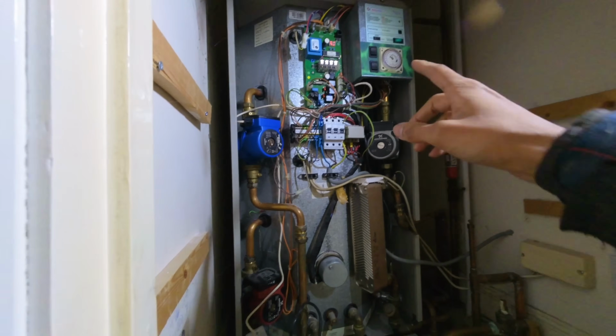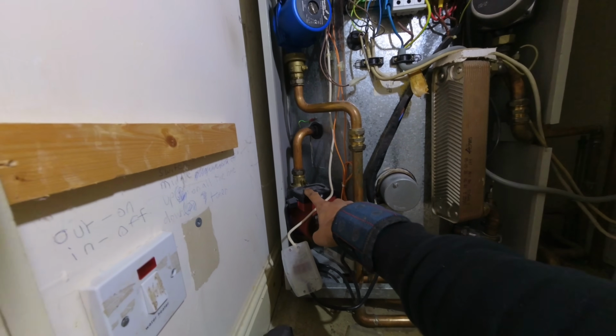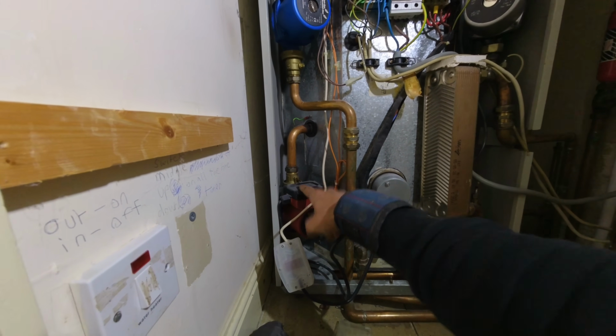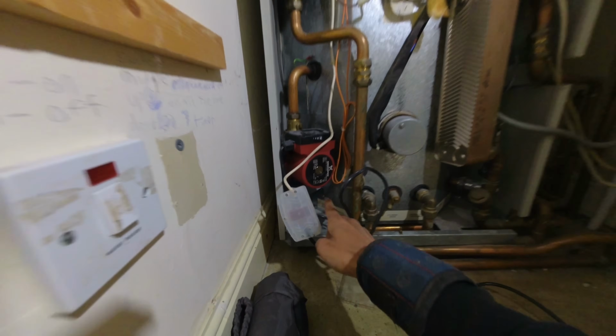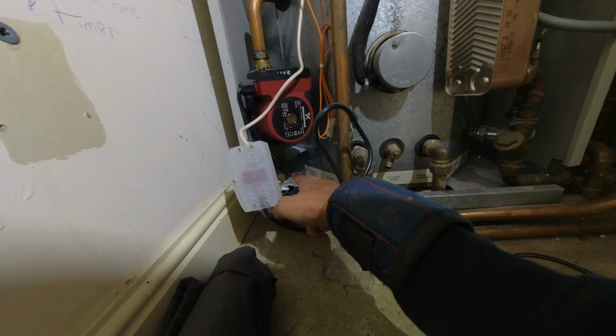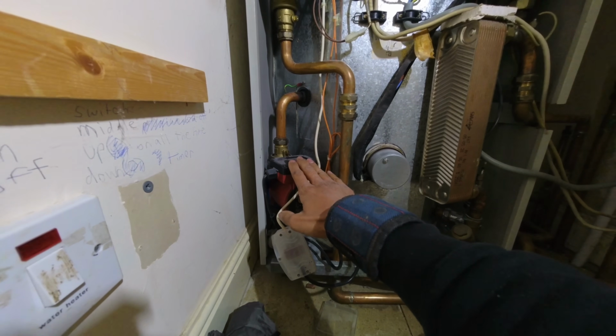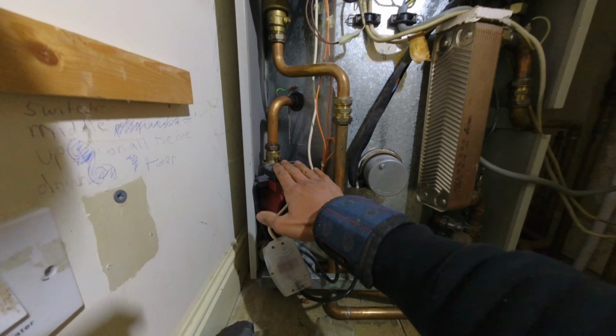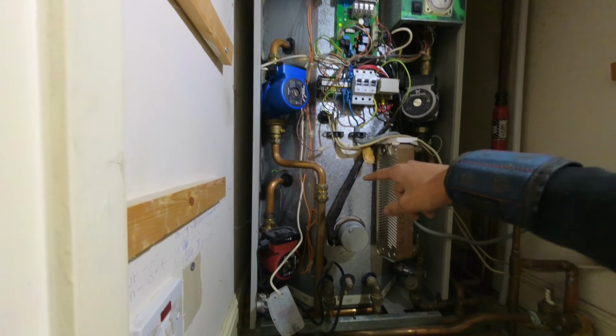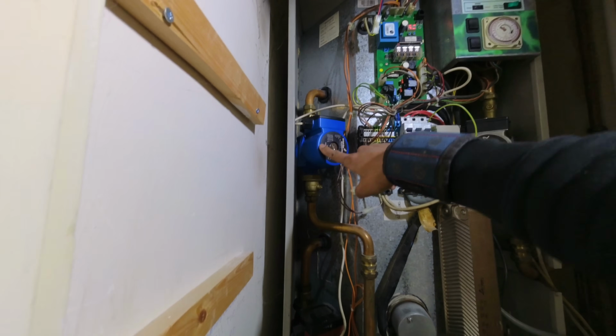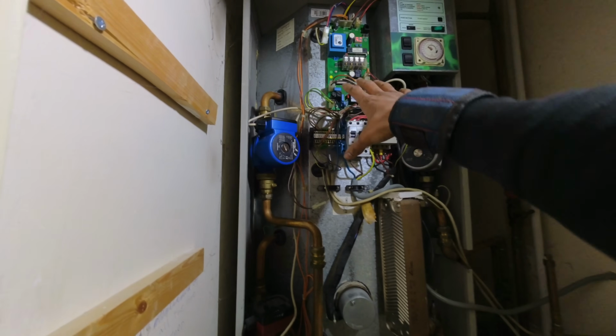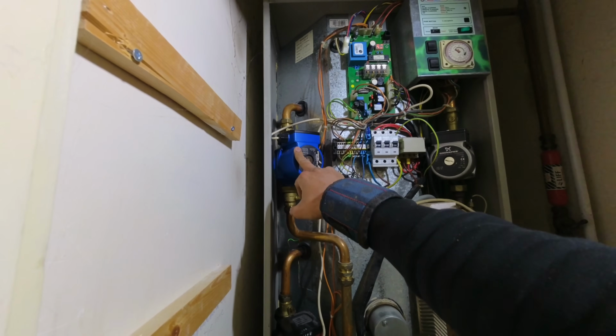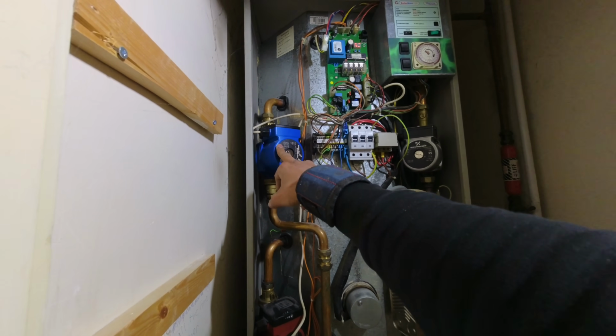So far, what I've checked is this is our main pump which circulates between the boiler and the store, and that's our primary return to the boiler. So that's what's meant to heat up the store. We've got our central heating pump here - when the store is satisfied and up to temperature, this will come on and start circulating heat towards the radiators.